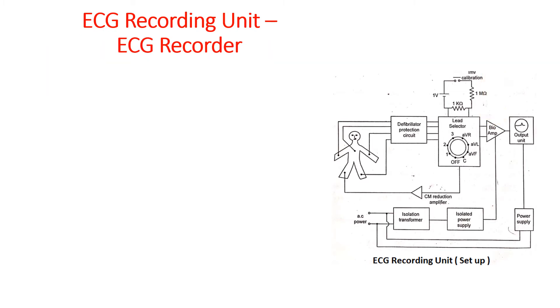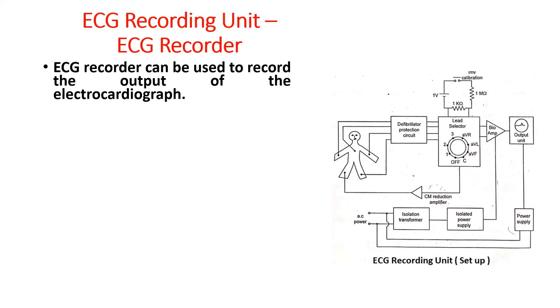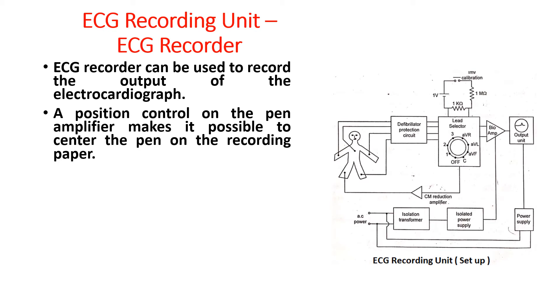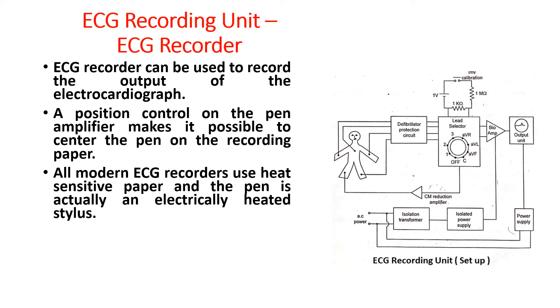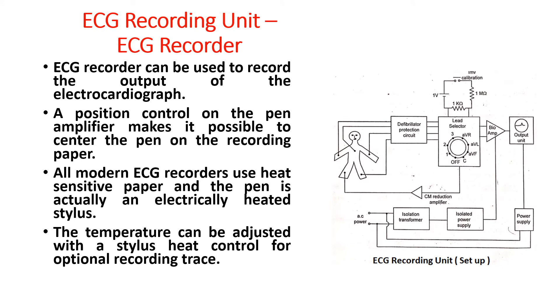ECG recorder. An ECG recorder can be used to record the output of an electrocardiograph. A position control on the pen amplifier makes it possible to center the pen on the recording paper. All modern ECG recorders use heat-sensitive paper and the pen is actually an electrically heated stylus. The temperature can be adjusted with a stylus heat control for optimal recording trace. Generally, an electrocardiogram is recorded at a paper speed of 25 mm per second, but a faster speed of 50 mm per second is also provided to allow better resolution.